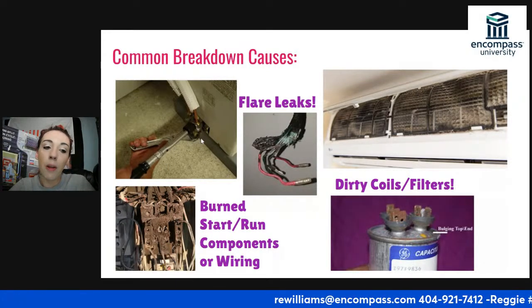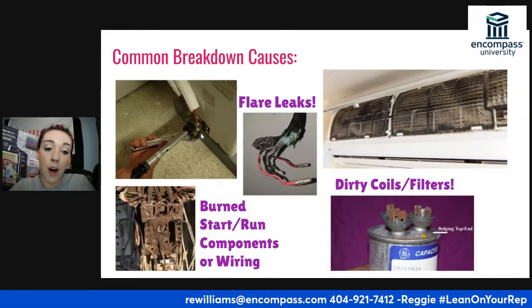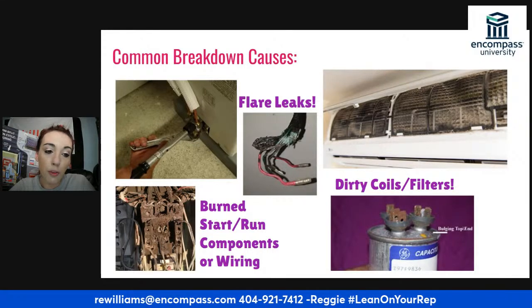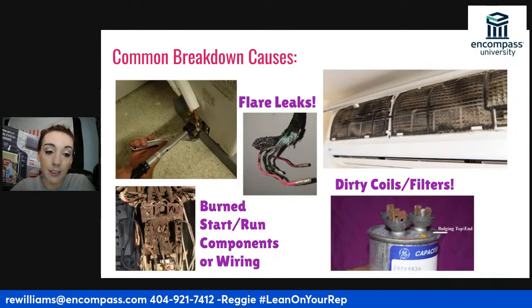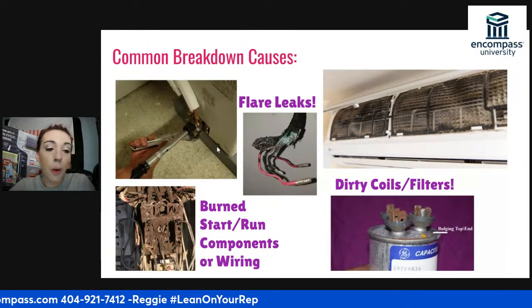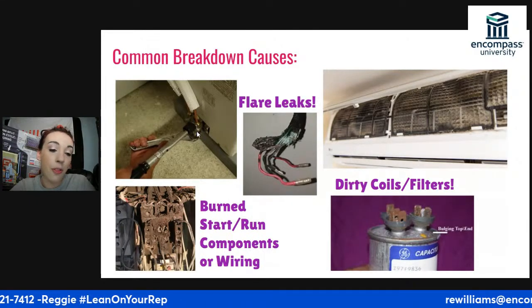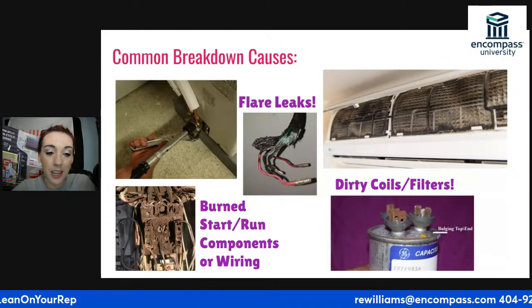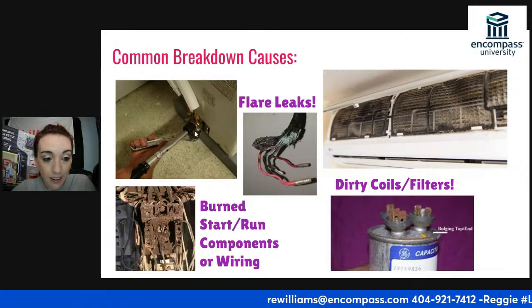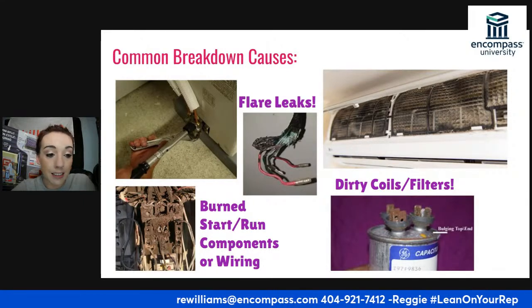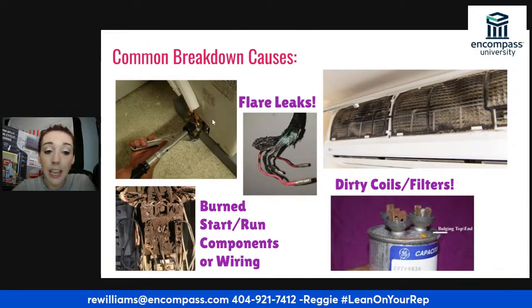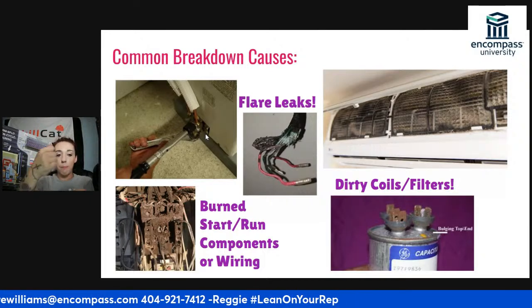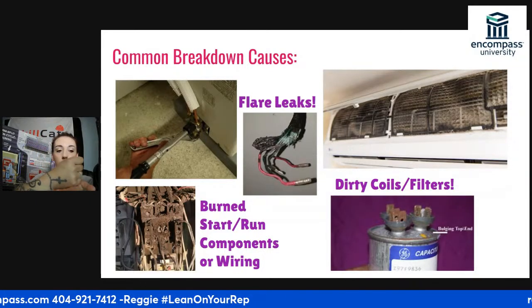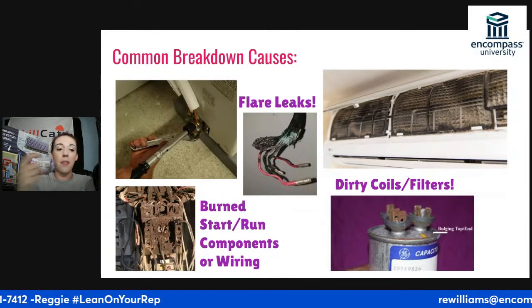That is what they do to keep the nut from falling off of the pipe and to keep you from losing it or from getting lost in transition to you. So when we get that pipe with that thing that looks like a flare and the flare nut on it, a lot of times we don't know that. So we will connect it as is, as if it's a flare connection. It's not. What they do is they put the pipe on a flat surface and they squish it. And that is how they keep the nut on.